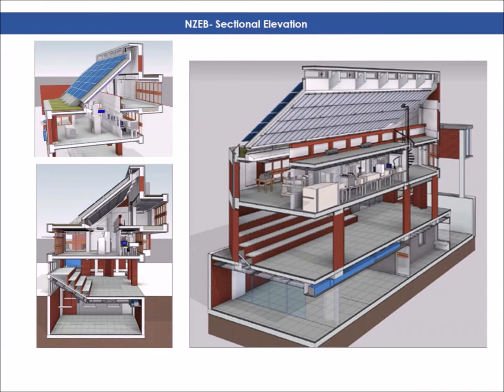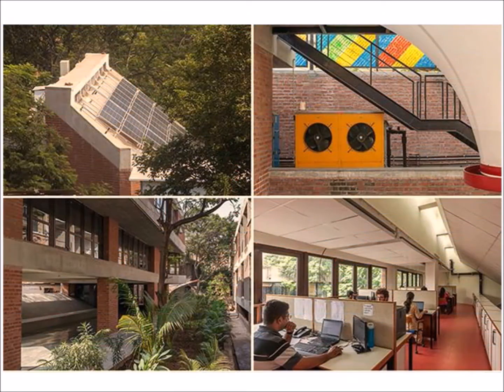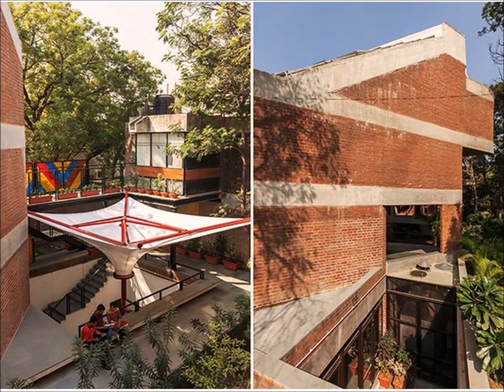One of the biggest achievements of CARBS is the designing and execution of a net zero energy building within the campus. This building is a living laboratory that serves for continuous and in-depth building energy efficiency research. It is operated in natural ventilation mode or in active system mode based on outdoor weather and indoor comfort conditions. It incorporates sophisticated control strategies such as demand ventilation, economizer based on enthalpy, chilled water reset, and chiller performance optimization.